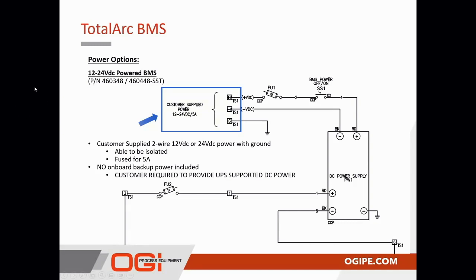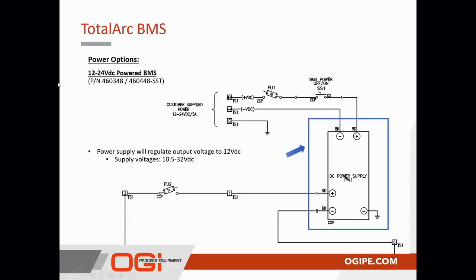In this case, as we talked about before, if there's a variation in power that comes to the BMS system, all power conversion is available or provided within the BMS system. Here's another good example of this. We have a power converter that's able to take a variation in power from 10.5 volts to 32 volts and maintain a consistent 12 volt DC output. If the voltage were to fall below 10.5 or exceed that, obviously we'd have safety factors there that would shut down the unit. Anyway, at this point, it really provides a wide variation of what's available for you.